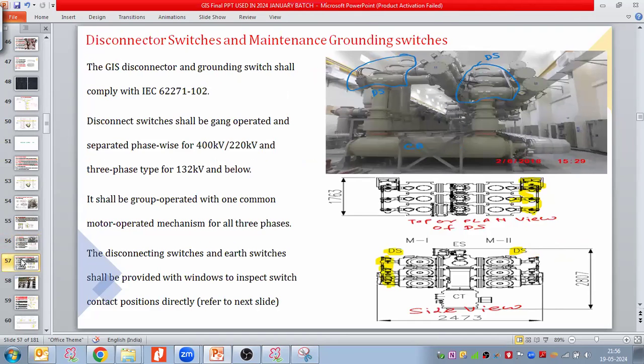Let us take the next equipment module: the bus bar disconnectors and the maintenance grounding switch. The GIS disconnectors and grounding switch shall comply with IEC 62271-102, same as in the AIS. Nothing changes, just the installation is indoor. The disconnect switch or isolator shall be gang operated and separated phase-wise for 400 kV and 220 kV; as we already discussed, we take a single-phase arrangement for 400 and 220 kV and a three-phase type for 132 kV and below.